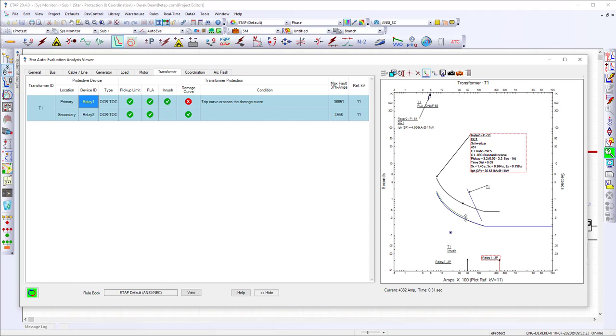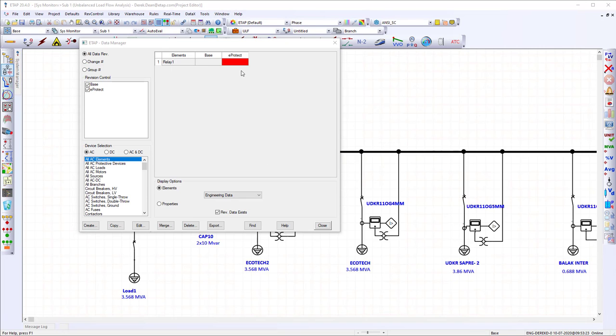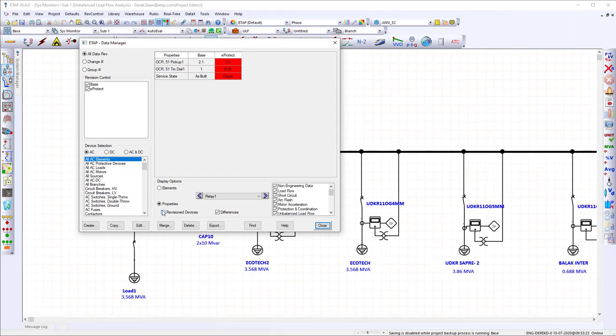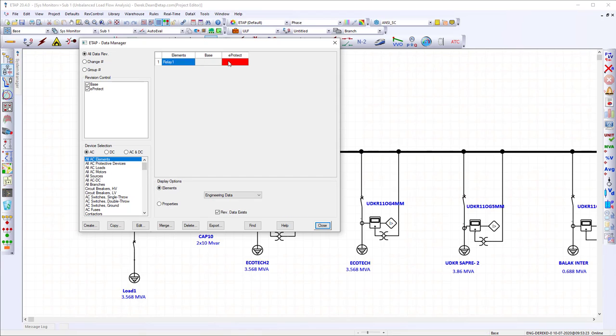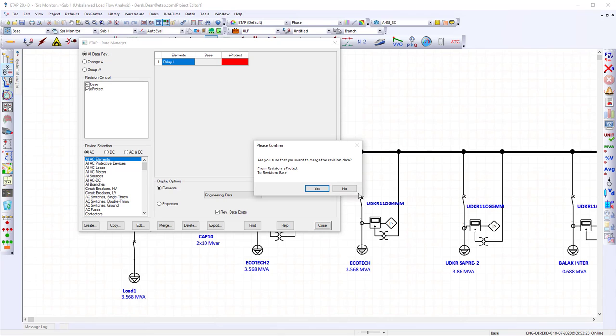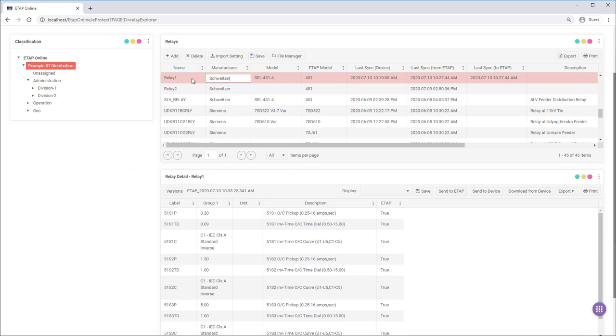Once I adjust the settings, Star Auto instantly updates to show me that all my protection settings are within limits. Now I can take my eProtect revision and use the data manager to take a look at the details of the differences. So when I select properties, I see the difference from 3.2 to 2.1 in my base case. And since we've updated this through a protection study, I can now drag it, override it to base, and update my base model with my eProtect settings.